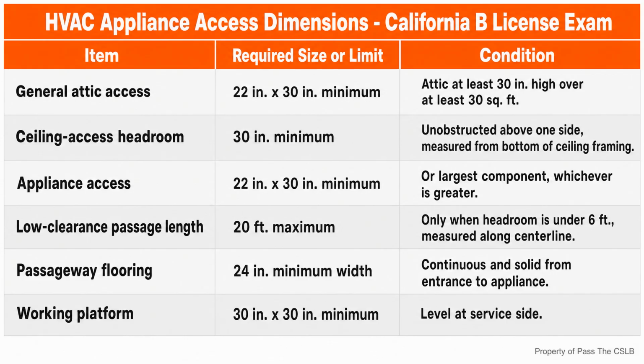A useful field question is this: can a technician arrive on the solid path, step onto a level 30 by 30 platform, open the required service panel, and remove the expected component without stepping off the platform or cutting another trade's work? That question does not replace the code or manufacturer instructions, but it exposes coordination failures quickly.